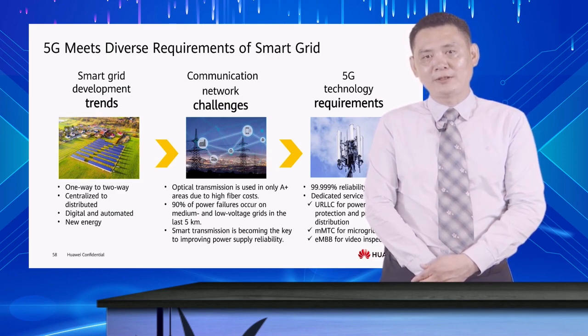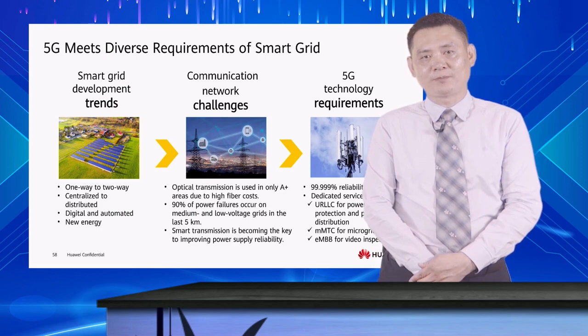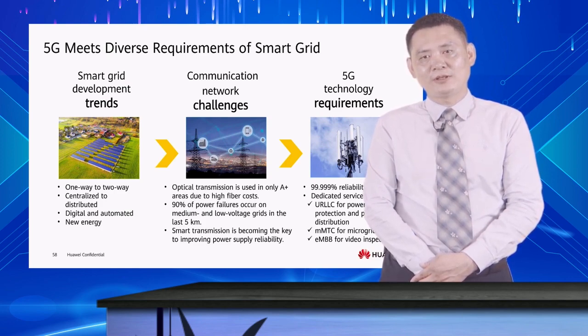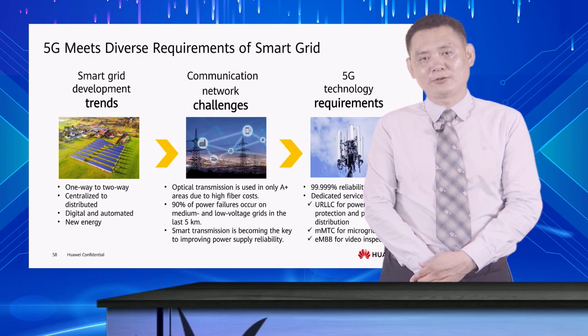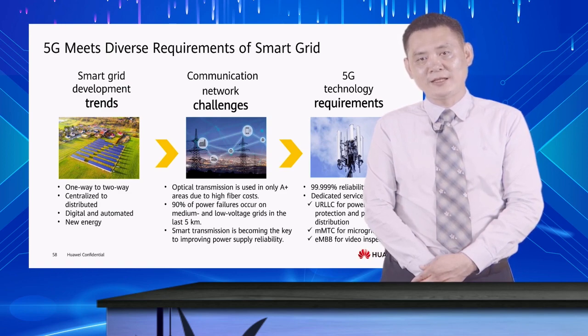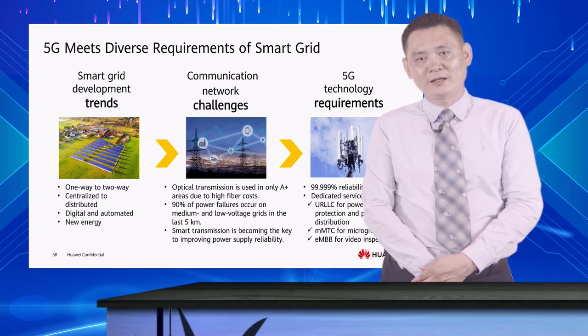Currently, the power grid communication network also faces some challenges. Optical fibers can only be used in the production areas to ensure high reliability while controlling cost. In actual scenarios, 90% of power failures occur on low-voltage grids in the last 5 km. The power grid communication network must have a reliability of 99.999%. In addition, network slicing is needed to meet the differentiated requirements for power grid services such as high reliability, massive connectivity, and larger bandwidth.